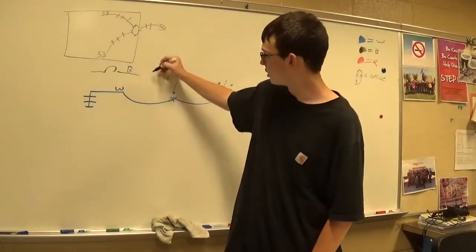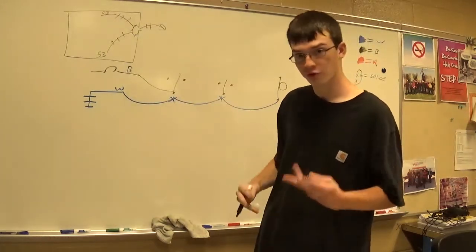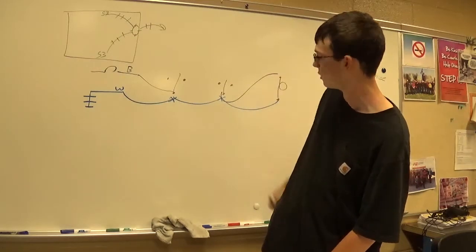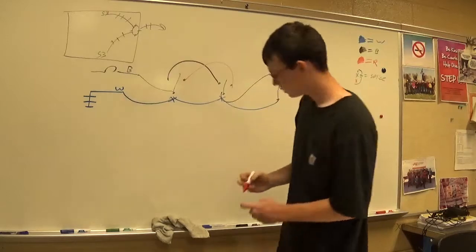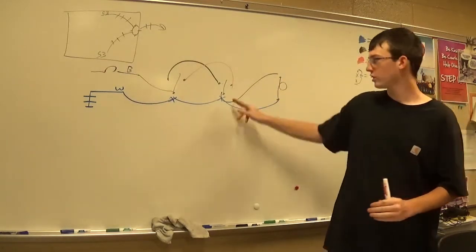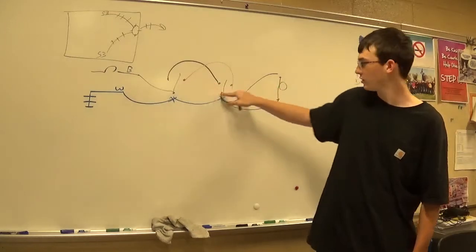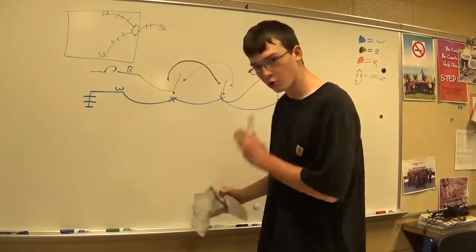Now your black will always come down to here, and then you have two travelers which gets power to this switch, which the black from this switch will come up there. You make sure you always connect it to the same poles of the switch, as you can see here. The red connects to the right, same thing here. Black is to the left, as you can see here.